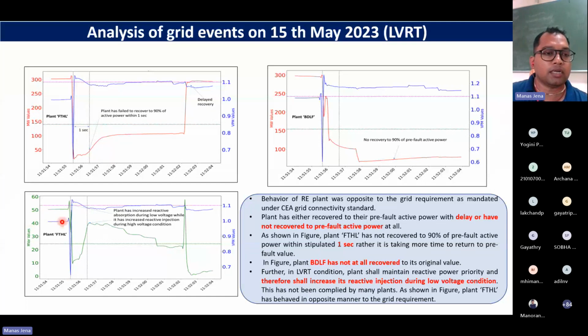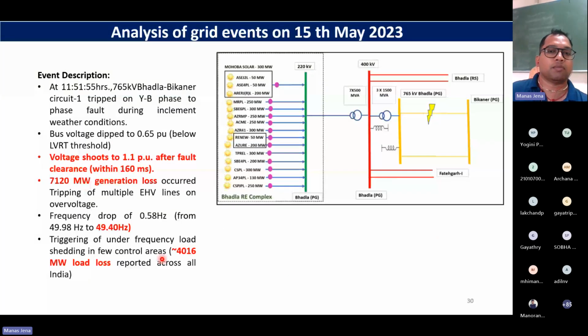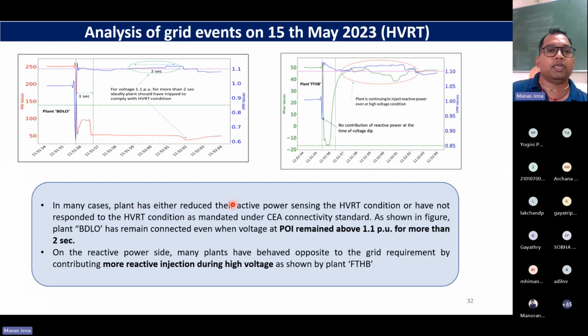When you are in LVRT, your MVAR should go up. When you see voltage is going up, you should absorb reactive VAR rather than injecting. If you operate in the opposite way, actually you are not helping the grid, and that is how these things happened. Okay, so a very interesting scenario. A few more slides. In many cases, plants have either reduced their active power sensing the HVRT conditions, or have not responded to the HVRT condition as mandated by our grid code.